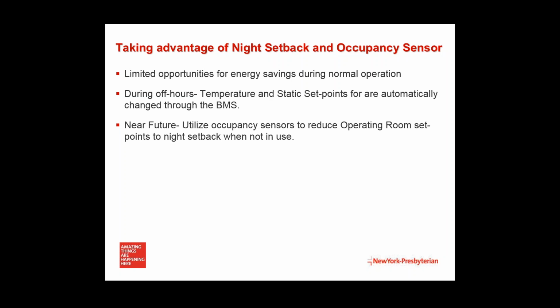Another feature we're looking at is the occupancy sensors to take advantage of during normal operations. The hospital has received capital funding to implement controls that will allow the same savings that occur during the night setback to take place whenever an operating room is not being used. Although these are minimal at times and opportunity, this could be significant savings if not utilizing the significant air changes and mechanical cooling capacities when a room is not being used.